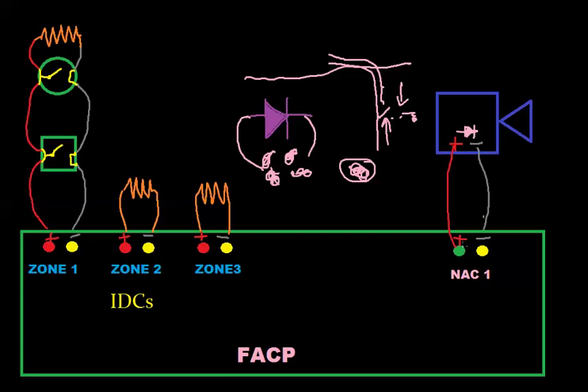Then it's going to go out to the end-line resistor. This would be a negative 24 volts. Since this is negative, it can't go through this diode. Even though it says positive right now, the voltage is actually negative, so it's blocked. It can't go through the actual horn strobe. It only goes to the terminals and through this resistor and back. It can't pass through this internal circuitry that we don't even see because it's tied to the horn strobe internally.